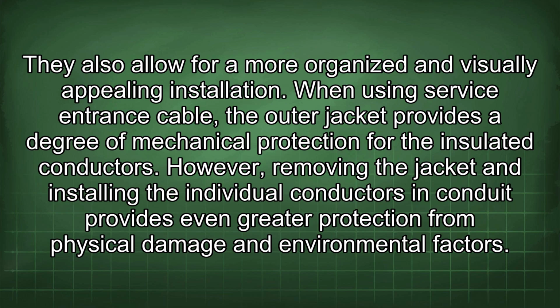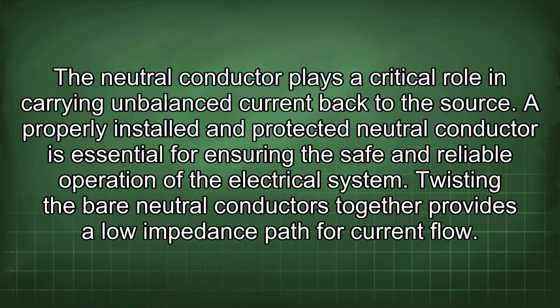When using service entrance cable, the outer jacket provides a degree of mechanical protection for the insulated conductors. However, removing the jacket and installing the individual conductors in conduit provides even greater protection from physical damage and environmental factors. The neutral conductor plays a critical role in carrying unbalanced current back to the source. A properly installed and protected neutral conductor is essential for ensuring the safe and reliable operation of the electrical system.